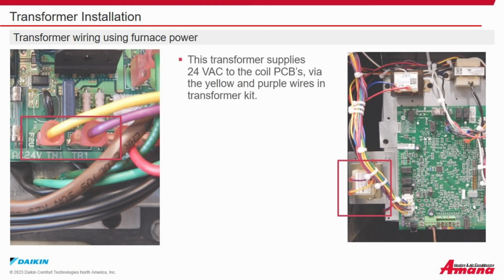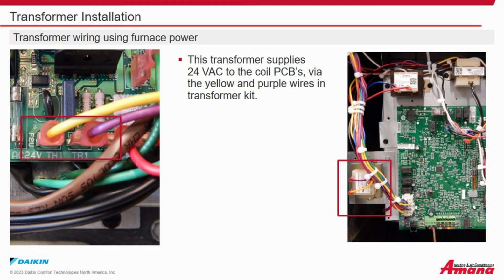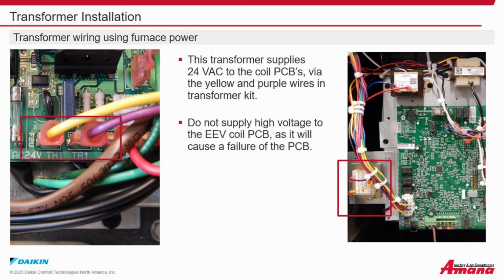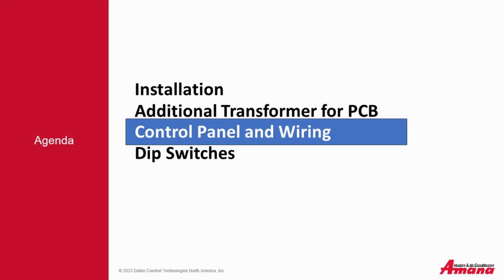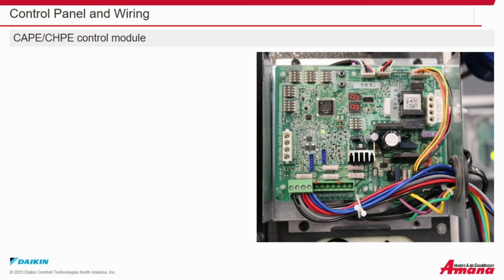Transformer wiring using furnace power. This transformer supplies 24 volts AC to the coil printed circuit board via the yellow and purple wires in the transformer kit. Do not supply high voltage to the EEV coil printed circuit board because it will cause the printed circuit board to fail. Control panel and wiring. The CAPE and CHPE control module.